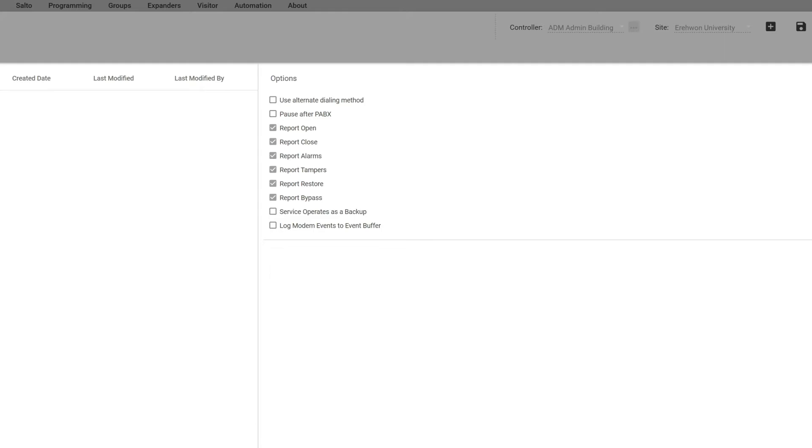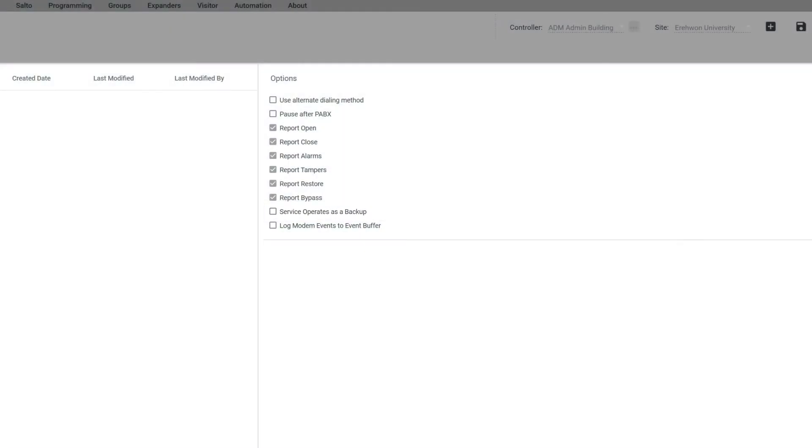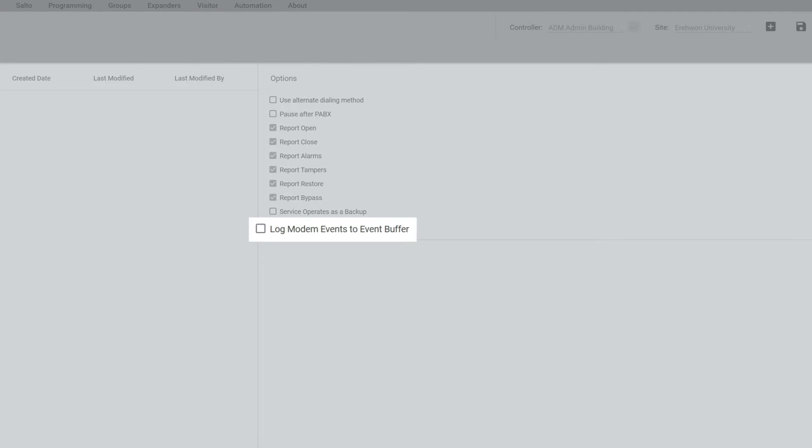Another thing to keep in mind is if you want the service to operate as a backup, you want to make sure that you click that. Also the log modem events to event buffer, if you click on that it's going to allow you to see all the communications that are going out to the central station whether it's successful or not. We recommend you don't check that right away. If you do check that, it's going to flood your all events window with just every single time it's trying to call out.